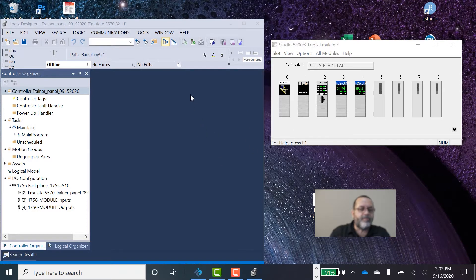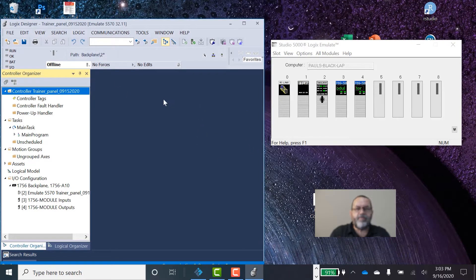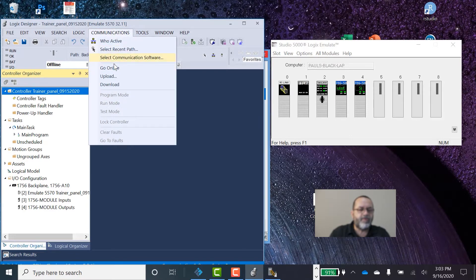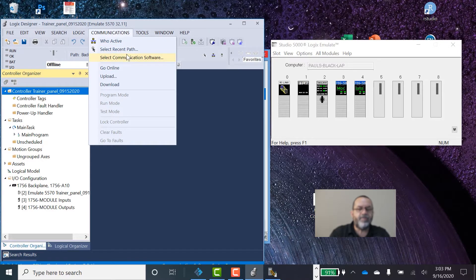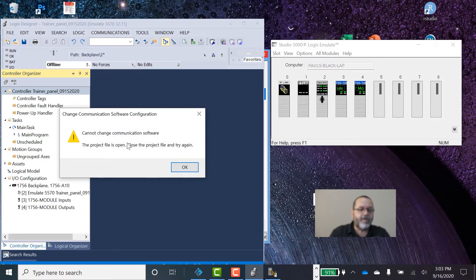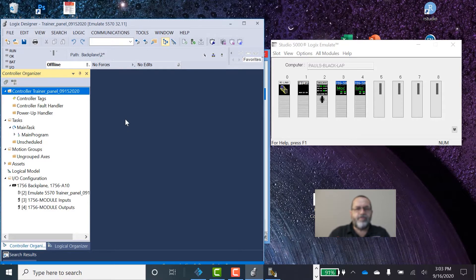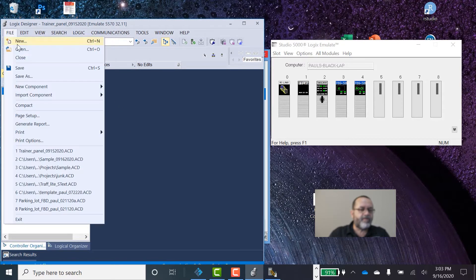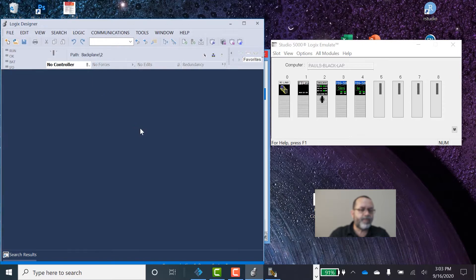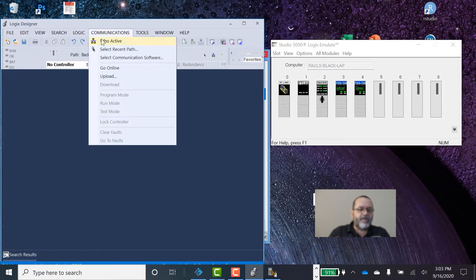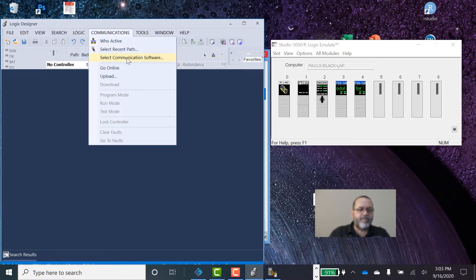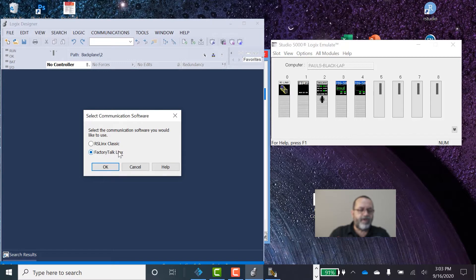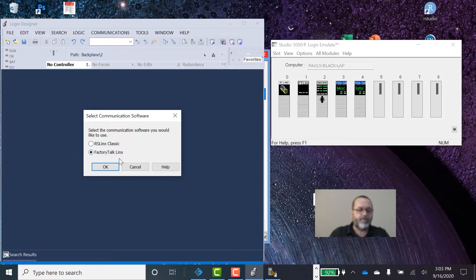Alright, first step is we need to set up Studio 5000 and what we want to do is under Communication, we want to select Communication Software. And when we try to do that, it's not going to work because we have a project open. So you want to close the project, don't close Studio 5000, just close the project. File, close. And once you do that, go to Communication, select Communication Software. And you want to change it to FactoryTalk Linx. Right now it's set on RSLinx Classic, we're going to use FactoryTalk Linx.